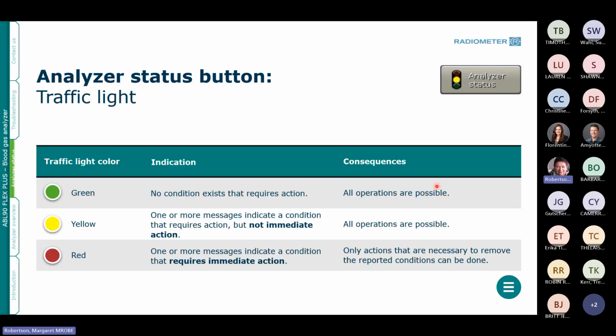Okay. All right, so then the analyzer status button, or our traffic light: if the light's green, no condition exists that requires attention. All operations are possible. Yellow means one of the messages indicates a condition that requires attention, but not immediate action. All operations are possible. And one or more messages indicating that something requires immediate attention will turn the traffic light red, and the analyzer will stop. At that point, you're going to have to stop and look and see what it's doing and what it wants.